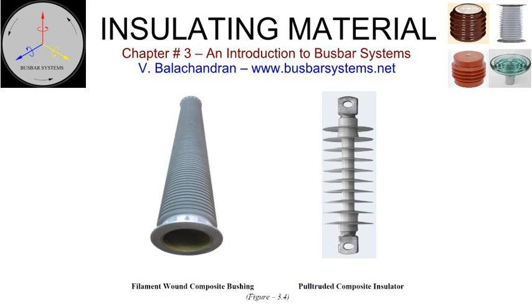Metal parts or flanges, normally made of spheroidal graphite iron, can be glued and attached as per the application requirements. The core can be inserted into a silicone rubber skirt of the desired profile to provide the necessary creepage. Composite insulators are significantly lighter than their equivalent porcelain counterparts.